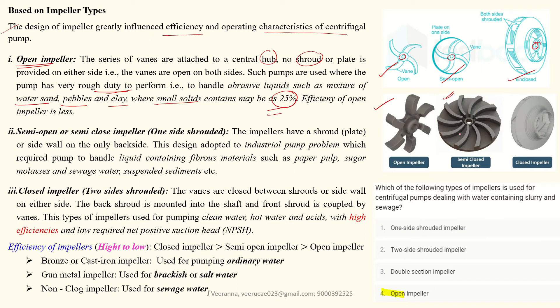The semi-open or semi-closed impeller has only one side closed — typically the back side — with a plate attached around the impeller on that side. This design is used for industrial purposes where the liquid contains suspended material, such as sugar molasses or sewage water. The efficiency of this pump is a little higher than the open type impeller.